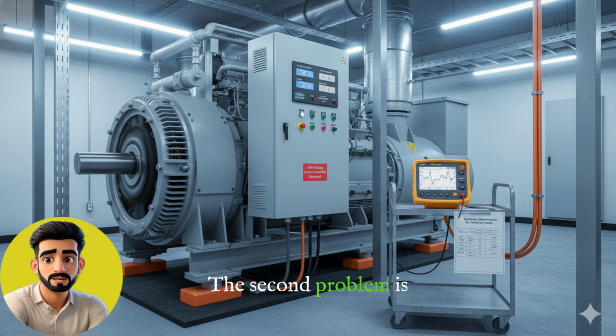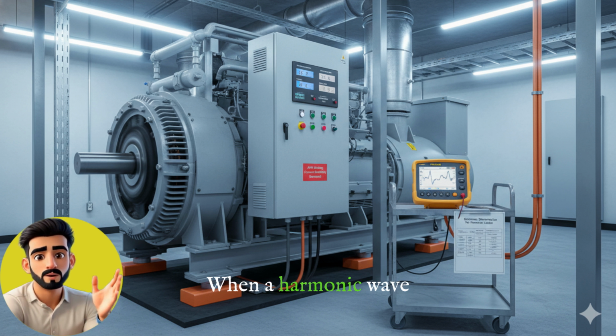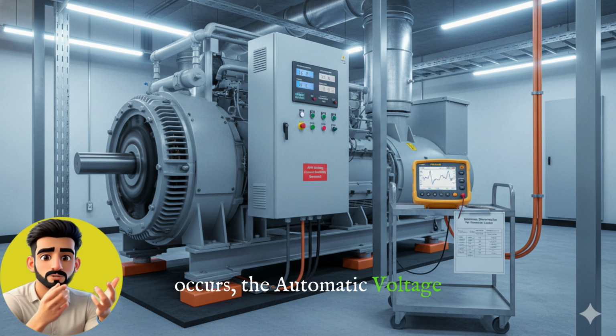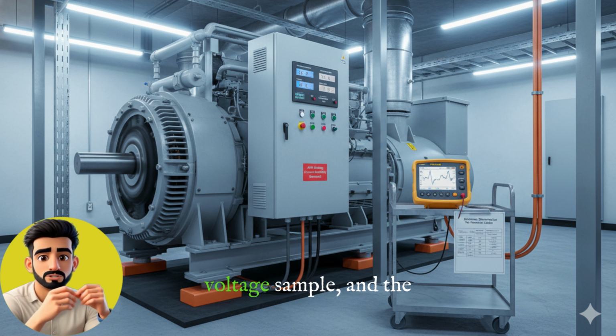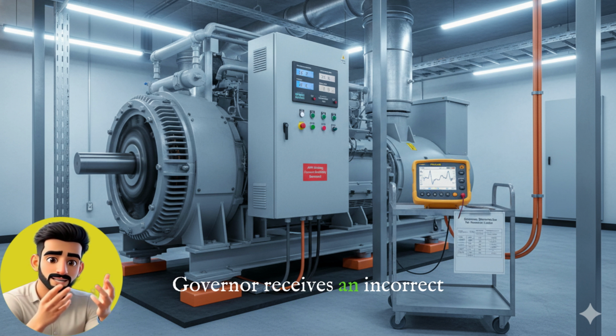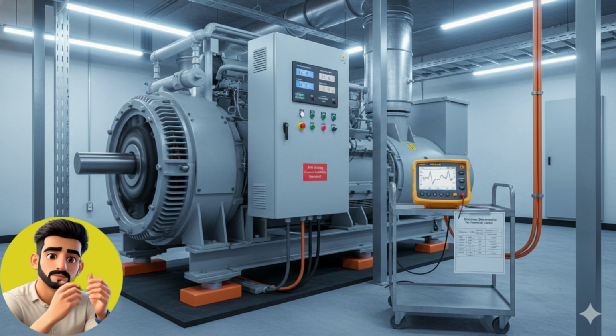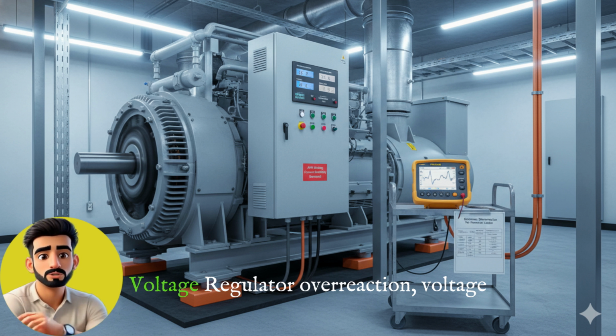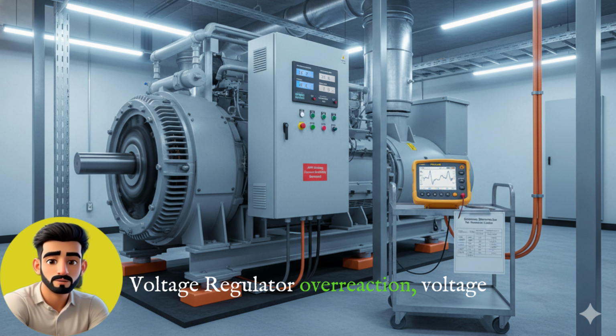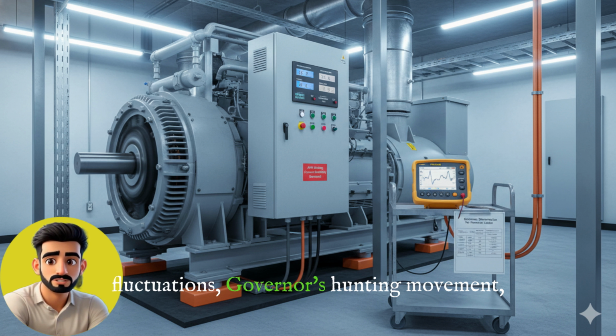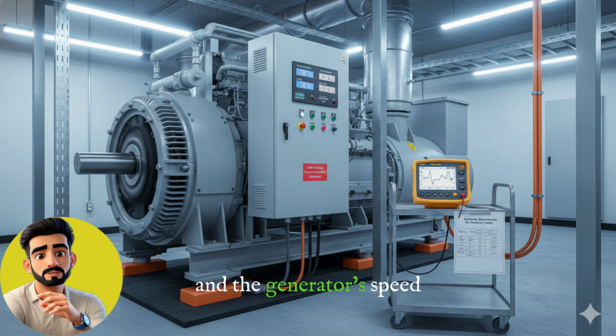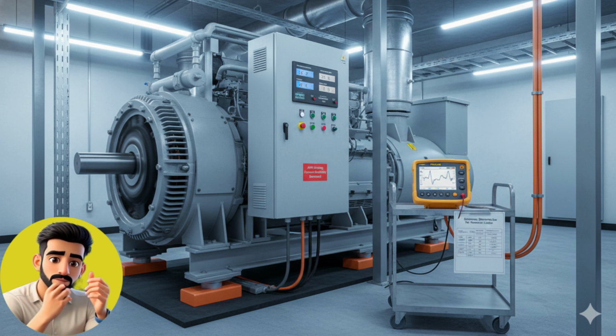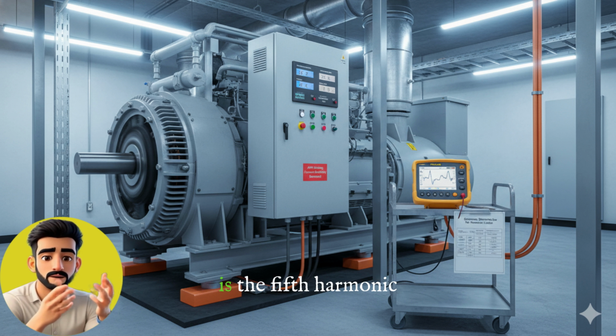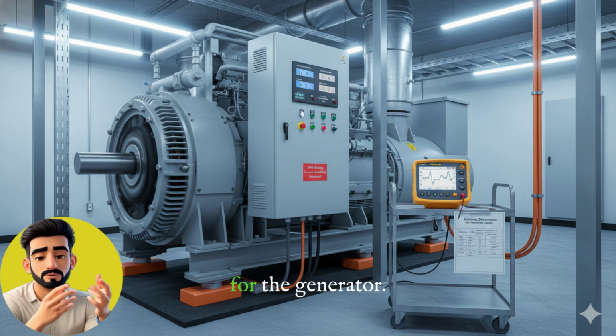The second problem is with the automatic voltage regulator and governor. Both controllers expect a smooth sine wave. When a harmonic wave occurs, the automatic voltage regulator receives an incorrect voltage sample and the governor receives an incorrect frequency sample. The result is automatic voltage regulator overreaction, voltage fluctuations, governor's hunting movement, and the generator's speed does not run smoothly. Another thing to understand is the fifth harmonic is the most dangerous for the generator.